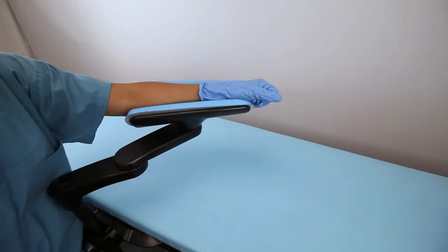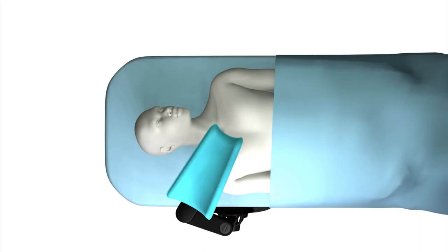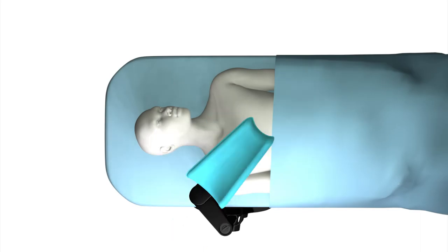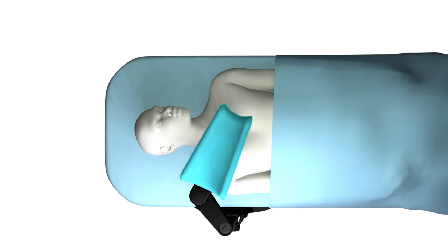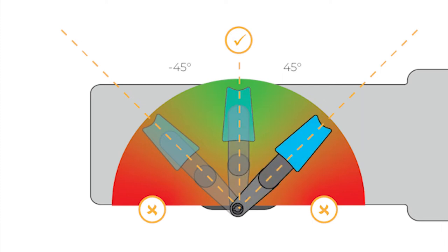Locked rigid or left free, the low-friction movement enables the clinician to manipulate the endoscope freely, providing a level of maneuverability on the horizontal plane to suit their needs. This pivoting arm arrangement allows the forearm support to move over a range of positions over a standard table's complete width.